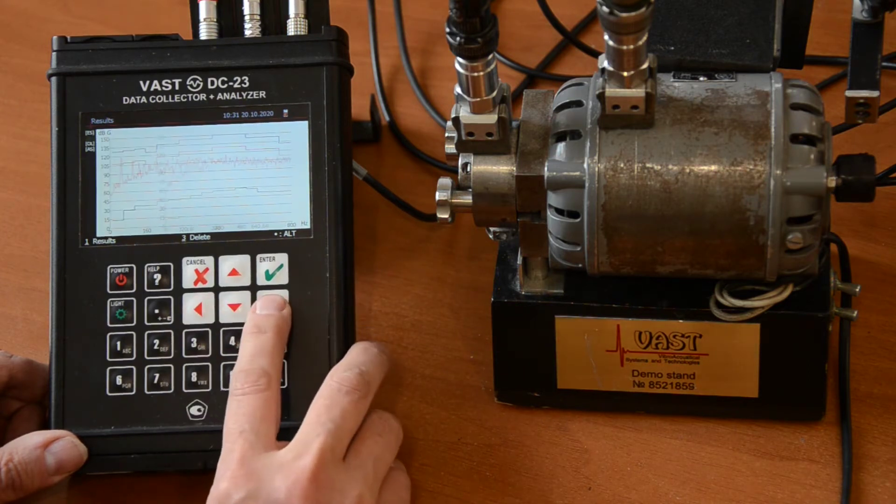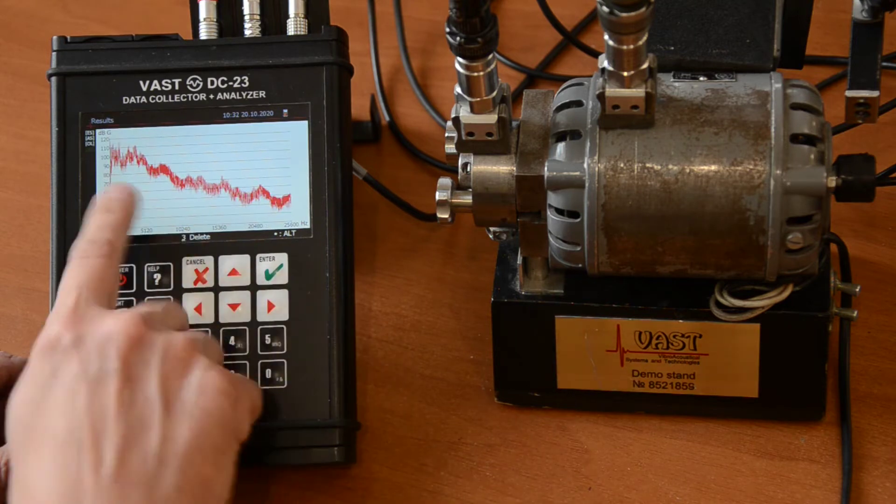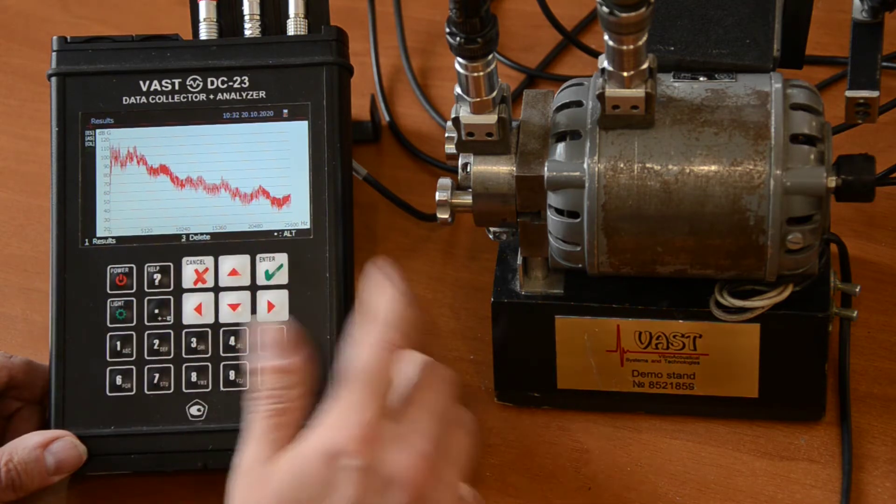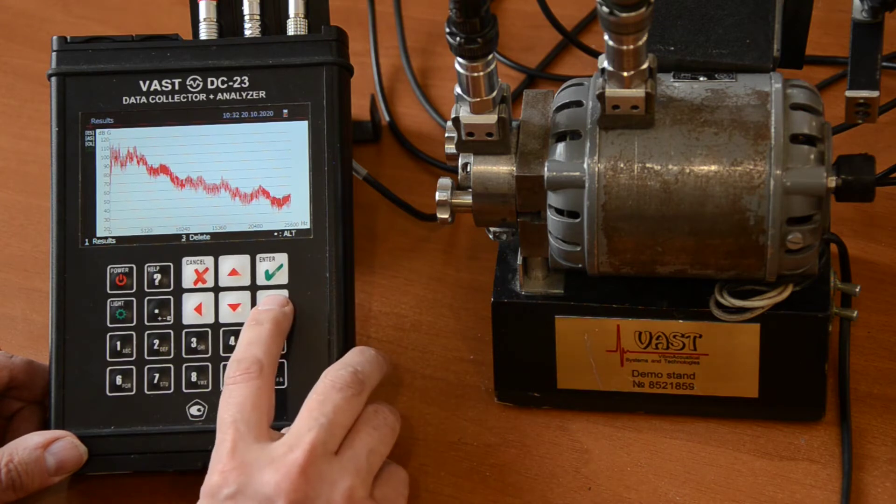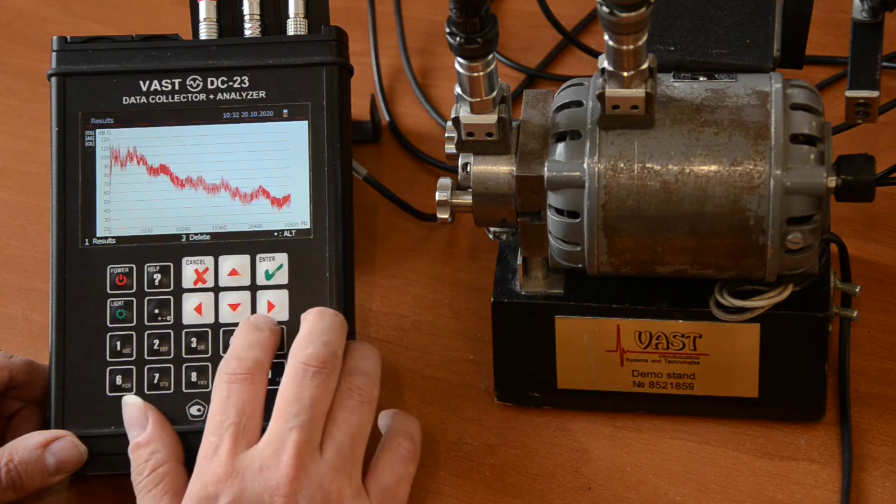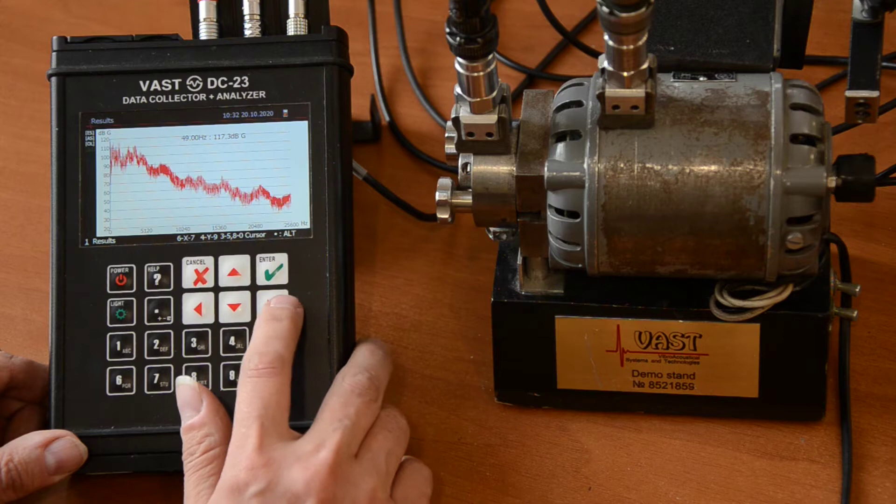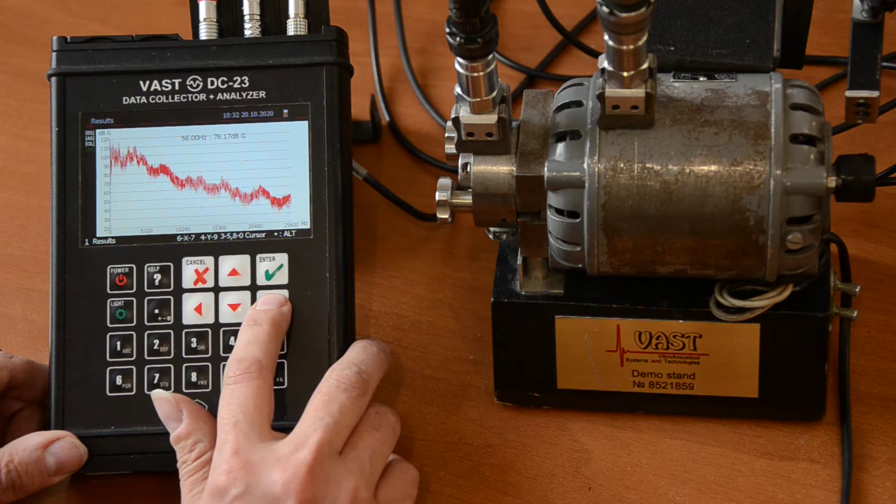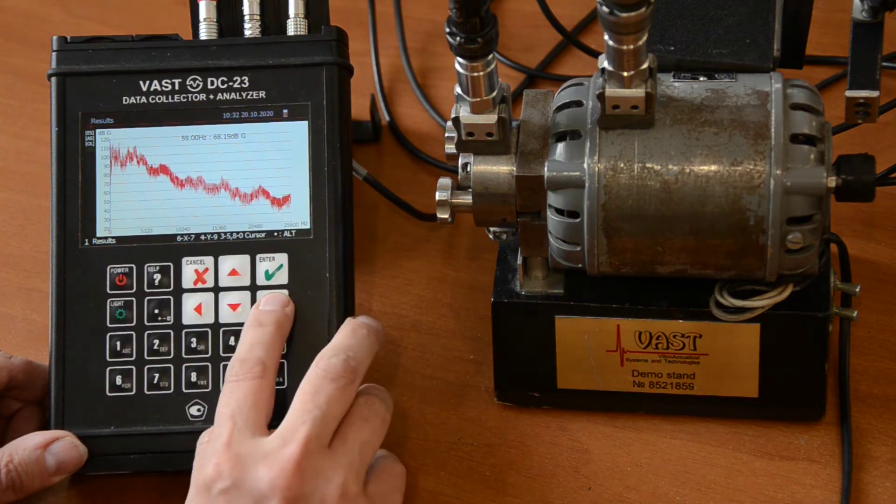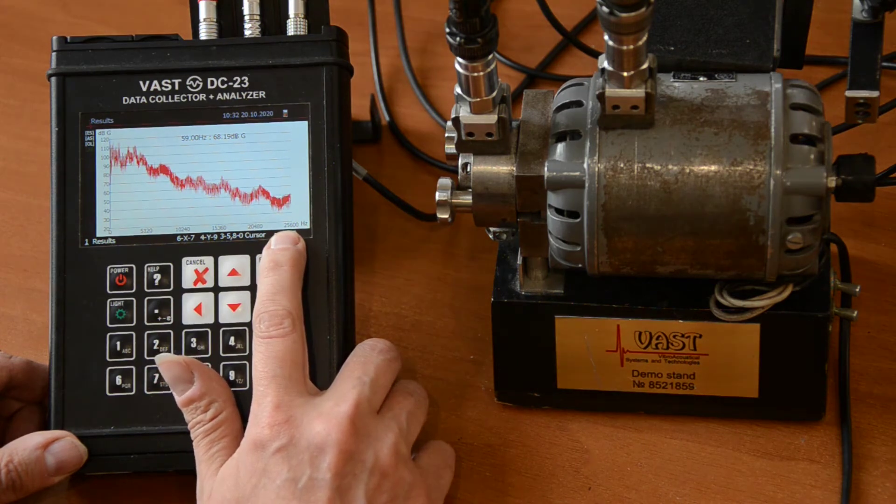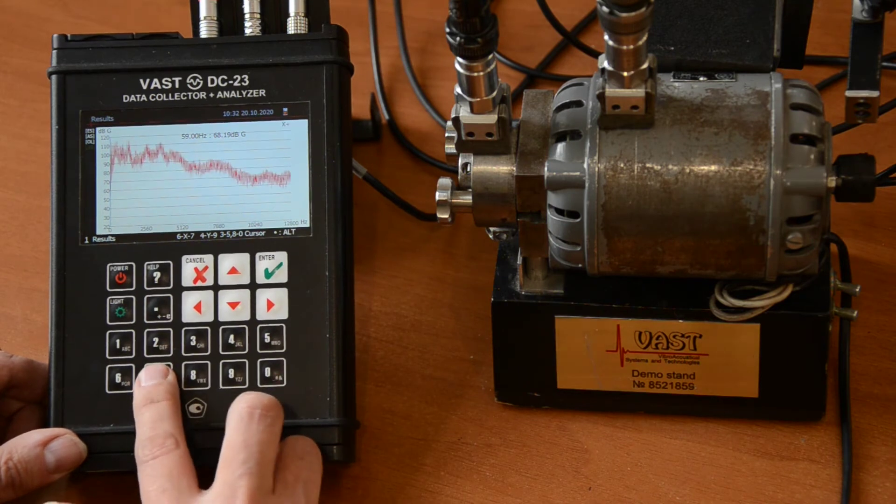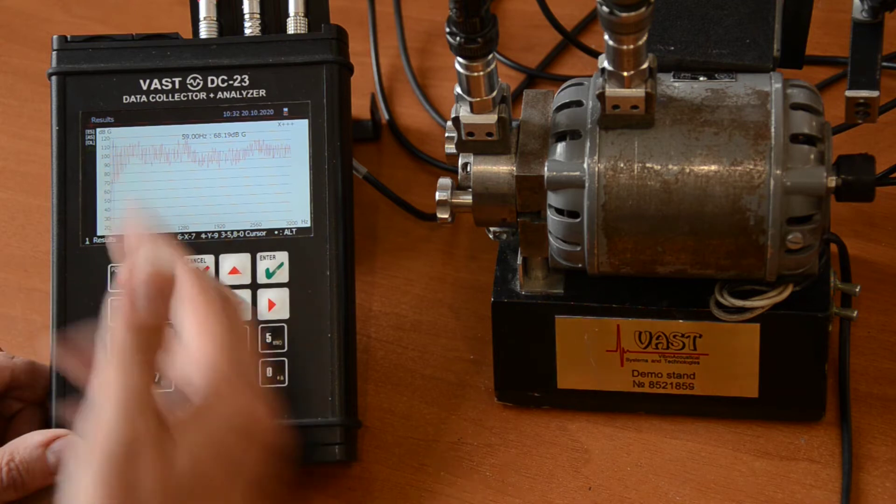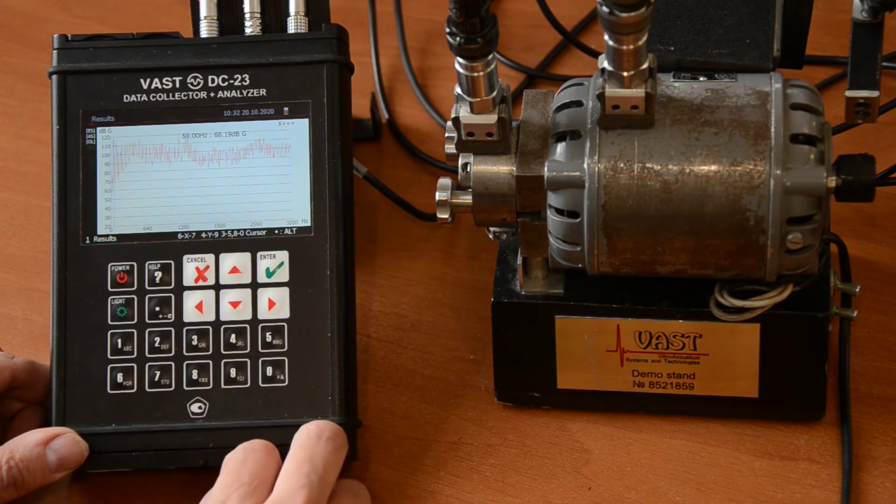We also have here an auto spectrum up to 25 kHz that we have programmed to measure. And the frequency resolution of this spectrum is about 1 Hz. So if we go back to this spectrum and we go to the analysis of it, you see that we have a very 1 Hz frequency resolution. This is the cursor position. This is 1 Hz frequency resolution up to 25,000 Hz. So this is 25,000 lines, actually. You can zoom it around the cursor and see what is there in this very spectrum.